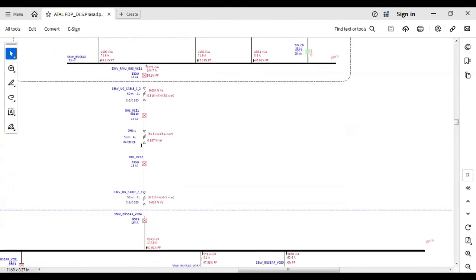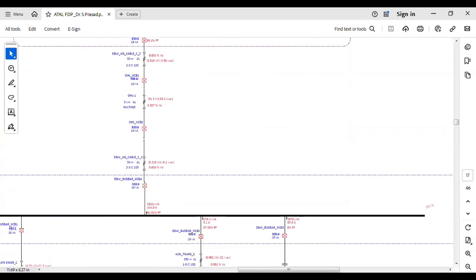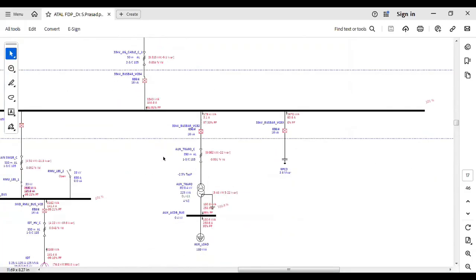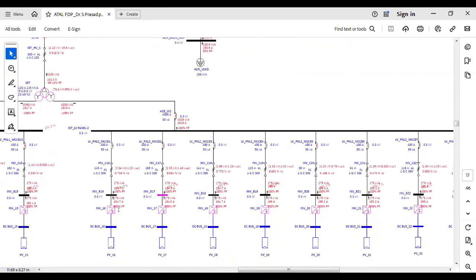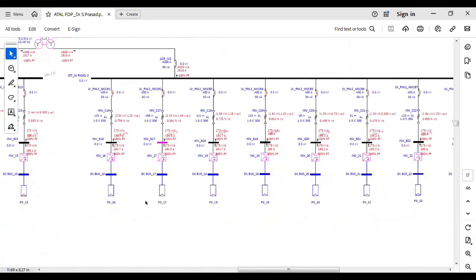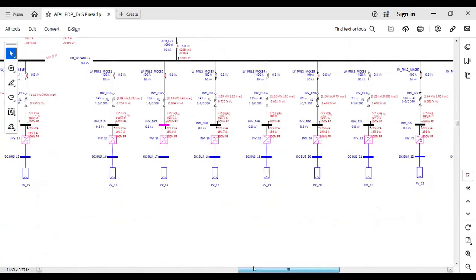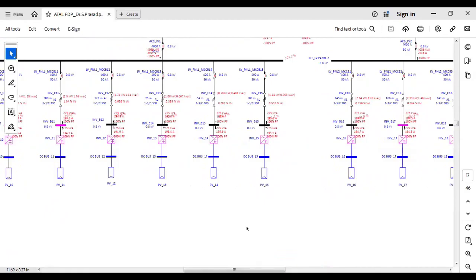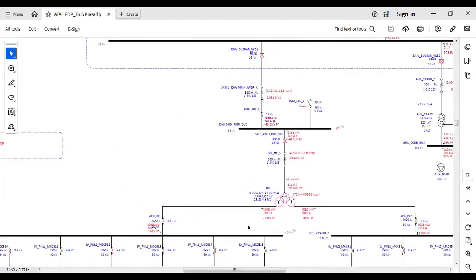Here you can see the transmission line. What is the loss happening in the transmission line? What is the voltage drop in the transmission line? Here we can also vary the inverter power factor to meet the required power demand at the point of interconnection. So we conduct this to know the total losses in the system and the voltage profile at all the buses of the PV plant, whether it is within limits or not, and whether any cables or the transmission line are getting overloaded. That needs to be verified by conducting load flow analysis.